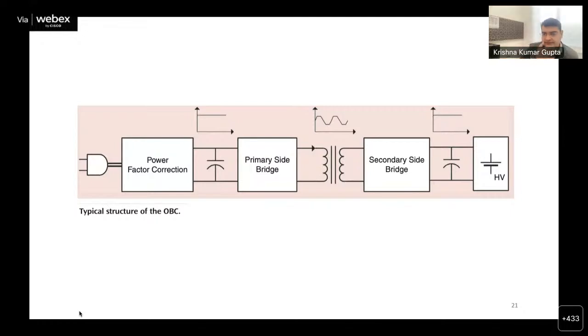In this diagram, the AC is first converted to low frequency DC. Then this DC is converted to very high frequency AC in the range of 20 kilohertz to 1 megahertz. This high frequency AC is transferred to the other side through a high frequency transformer, and then converted back to DC, which is used to charge the batteries.